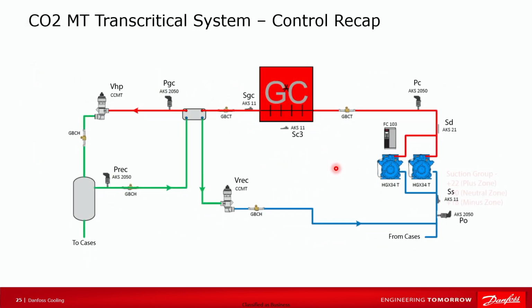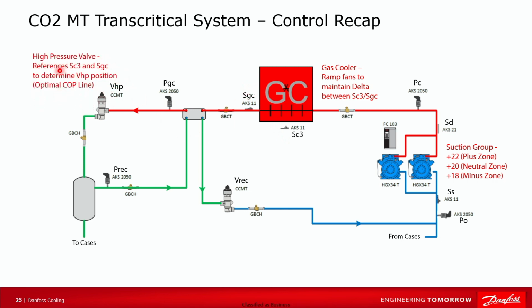So just a quick recap on the control, and we'll take some questions. Suction group, we're using neutral zone plus and minus control to control the compressors. We're ramping gas cooler fans to maintain a delta between these two sensors. High pressure valve references ambient and a lot of other things, but it's basically trying to keep the gas cooler outlet temperature on the optimal COP line, again, which is coefficient of performance. Higher the COP, the more efficient the compressor. And then the receiver valve opens and closes to maintain receiver pressure.